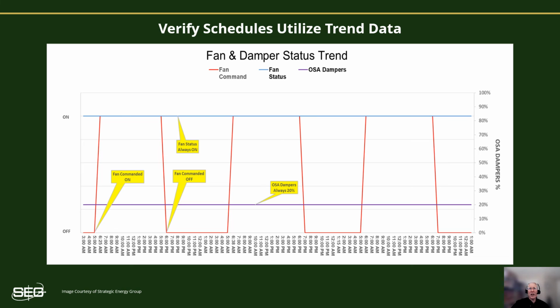This trend log is showing that the fan is stuck on and the outside air dampers are set for 20%, and it doesn't change. So not only is this fan system using electricity 24/7, but since the dampers are not shut after hours, the system is using energy to condition outside air 24/7. This will drive up both electric consumption as well as gas consumption. So finding and fixing the root cause of this one will likely be a very good energy saver.